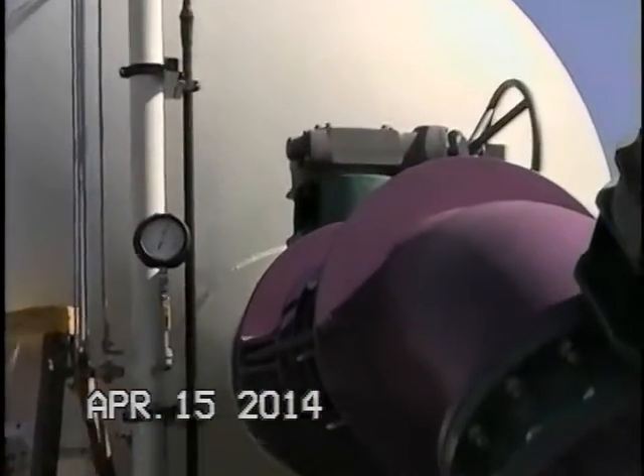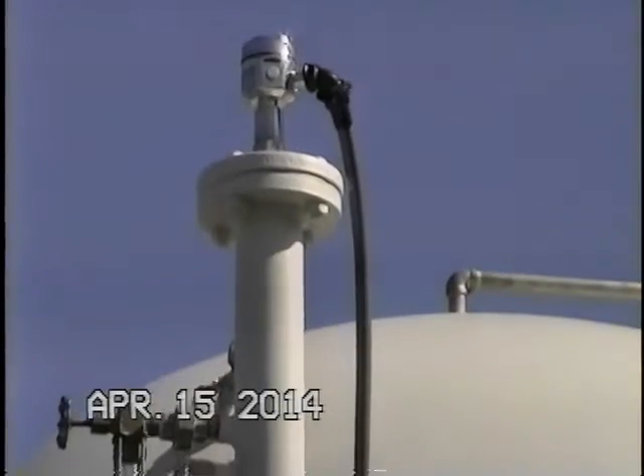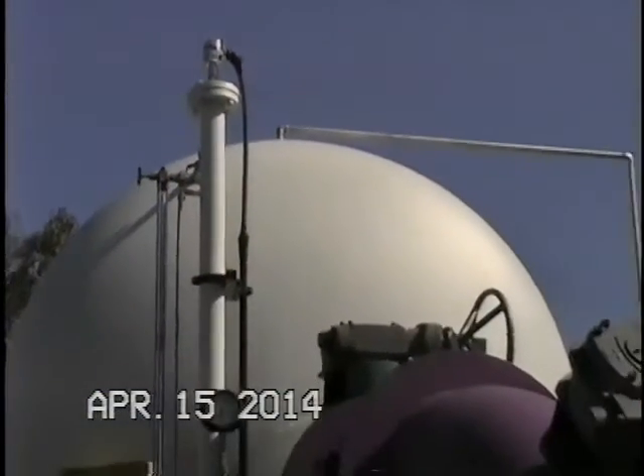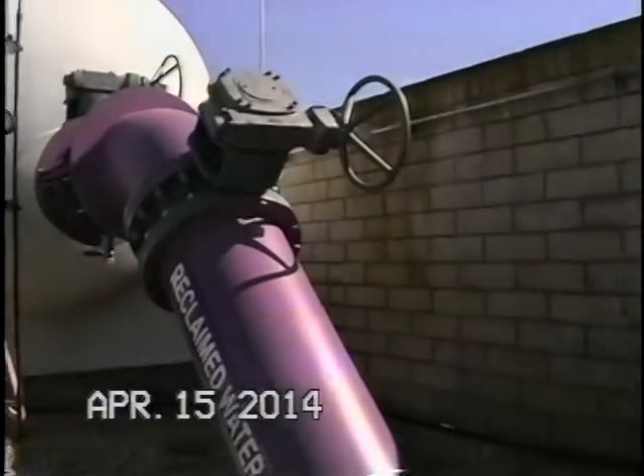pressure relief valve. In all cases, the working pressure of the surge tank is much greater than any anticipated surge we would see, plus we have a safety factor of 3 to 1 because it's an ASME code tank. The PRV at the top protects the tank from overpressurization of the compressed air system. That can typically only occur if the tank was isolated from the discharge pipeline, shut off, and somebody just turned the air on. That's the only way you can create excess pressure inside the tank.